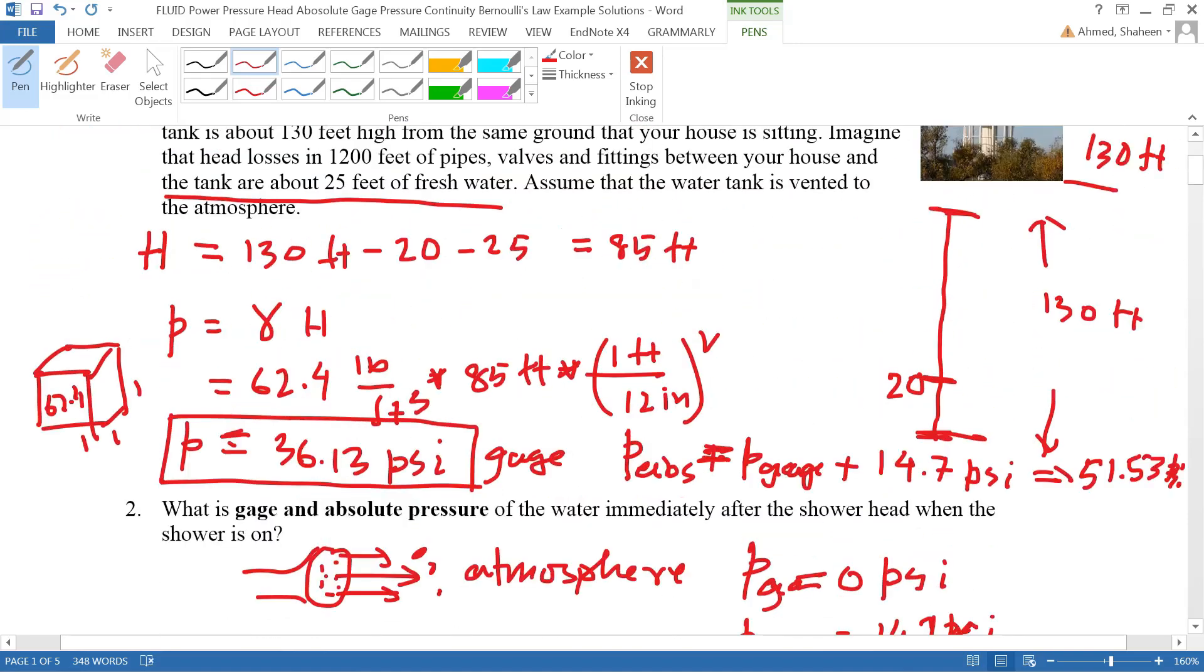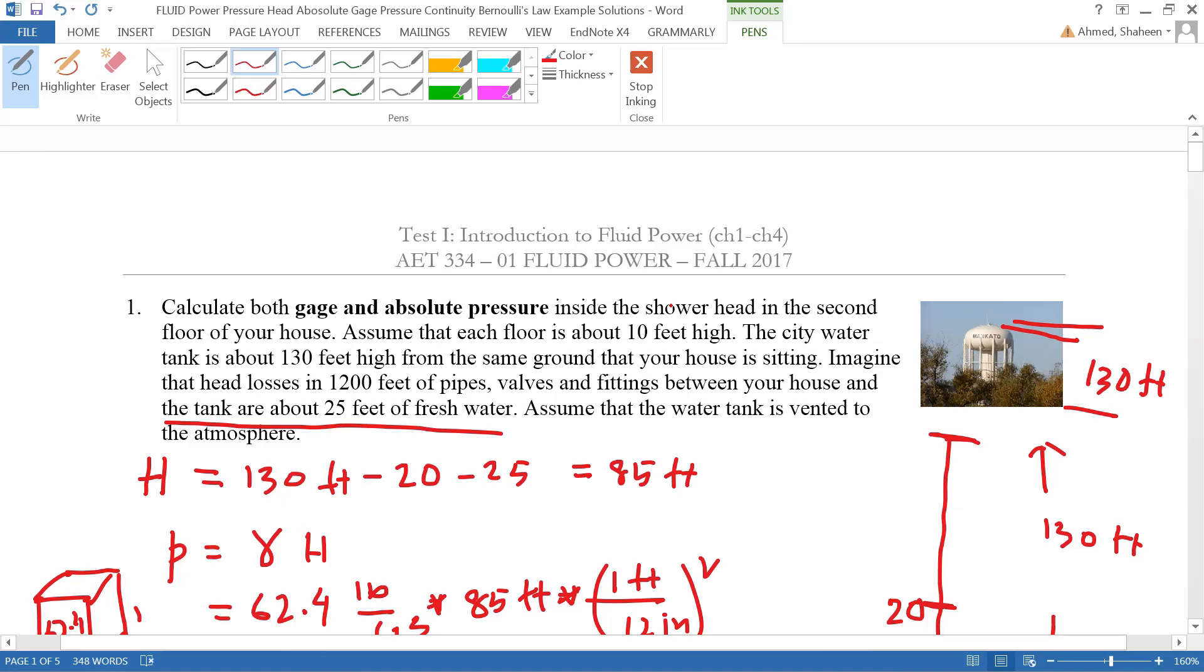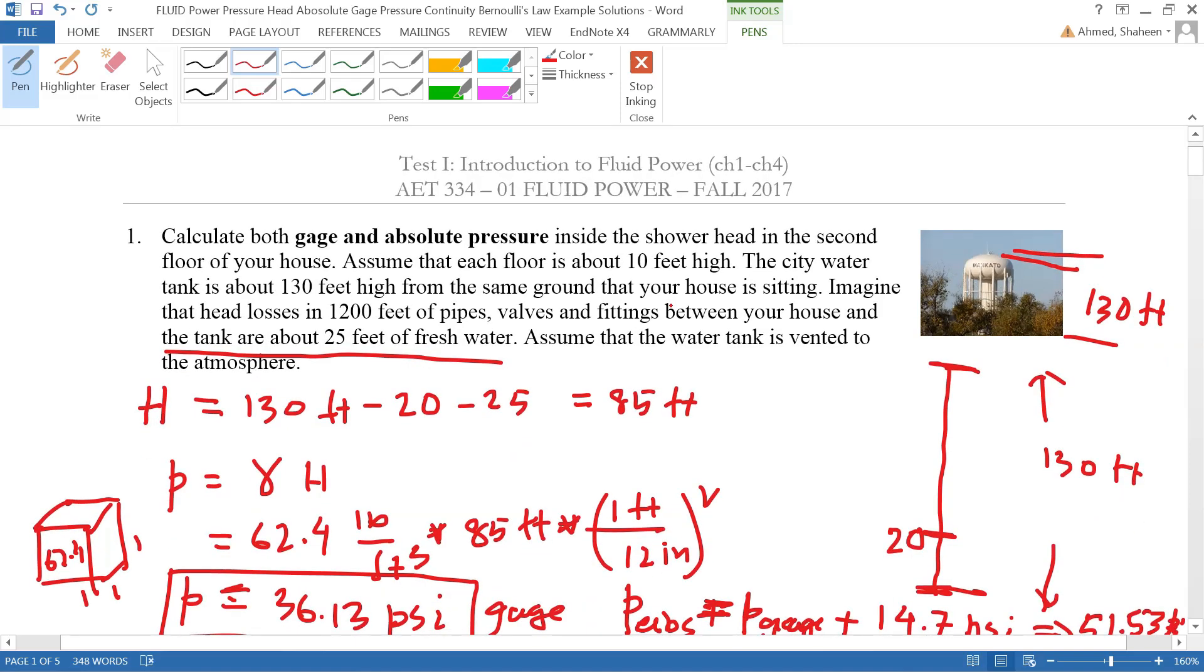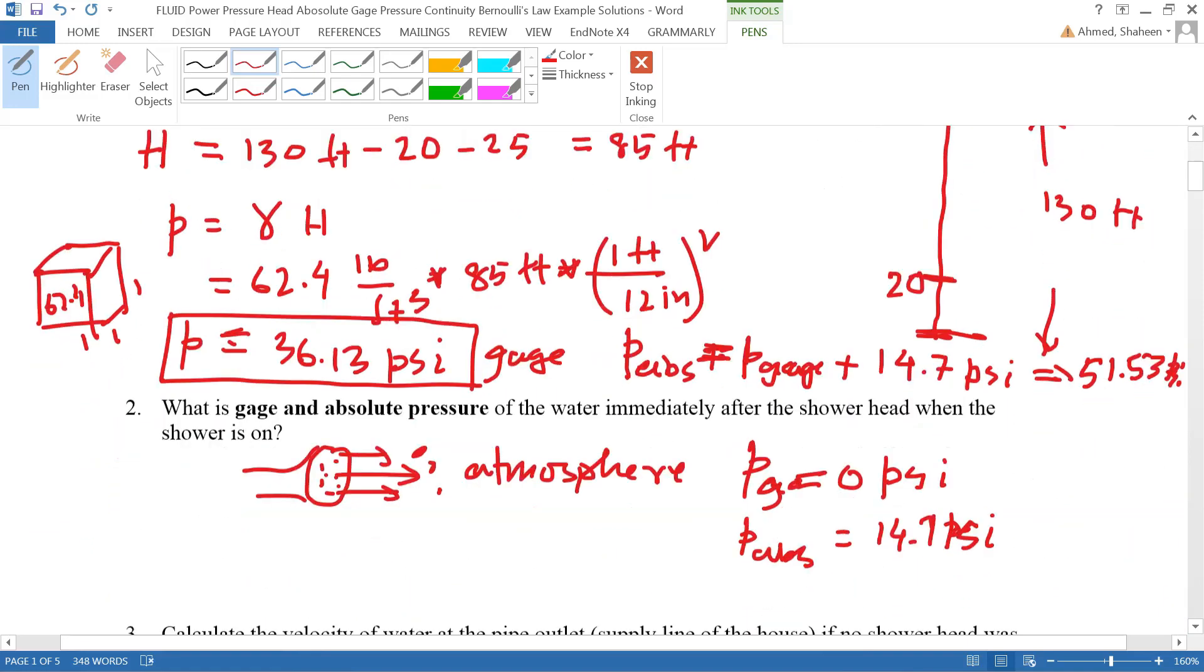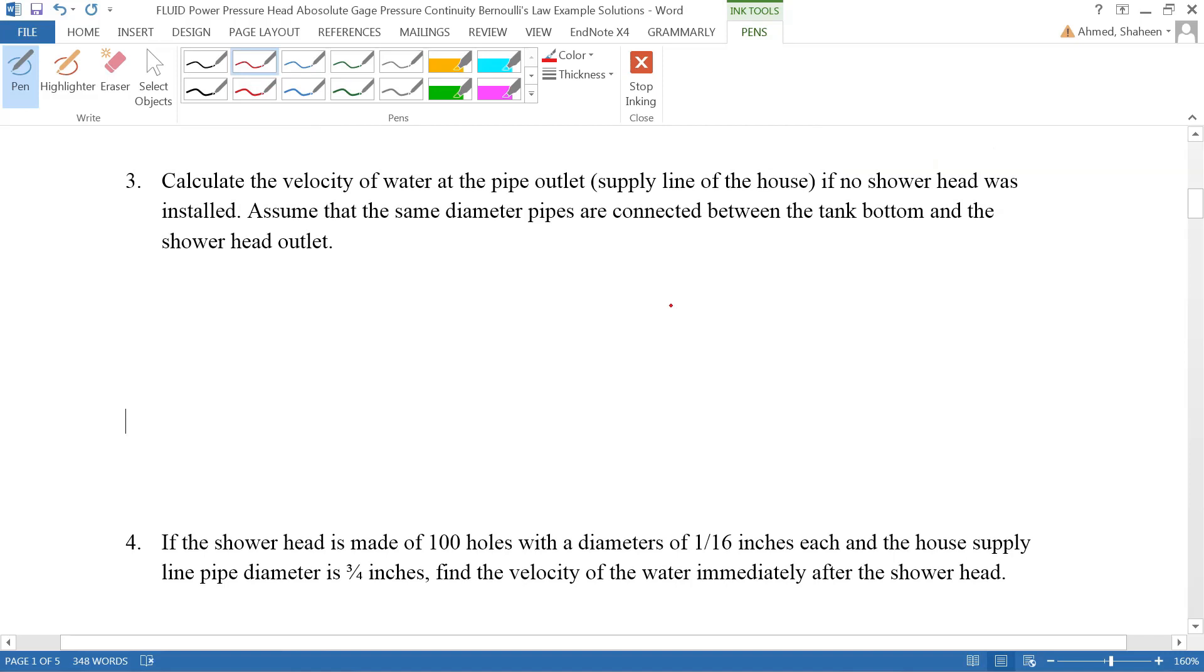So basically you have this 130 feet high water tank, 25 feet of loss between the water tank and the house, and then it's two-story high and the shower head is at 20 feet high. So the total head available here, in terms of the head, is 85 feet of water. That is what is available.